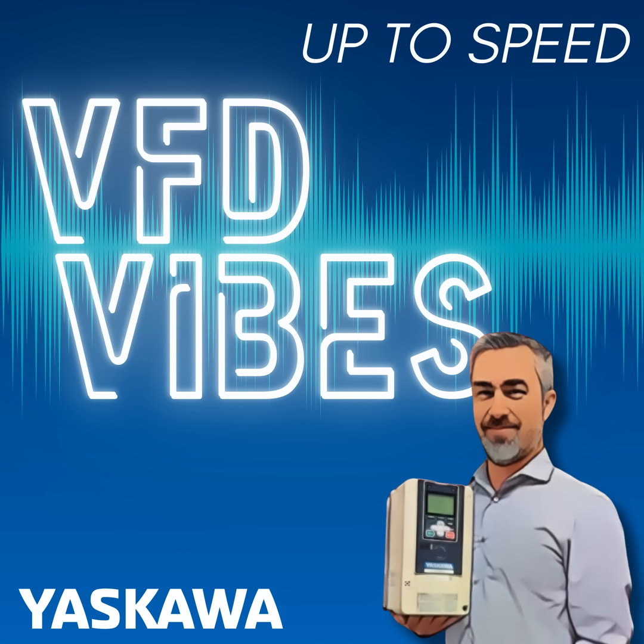Our listeners may be familiar with multi-pulse drive packages. These would be 12 or 18 pulse designs, and I use the word package because these aren't standalone drives. A multi-pulse drive package uses a phase-shifting transformer and additional rectifier blocks on the front end of the drive in the converter section to phase shift your incoming voltage so that you reduce your DC bus ripple and you reduce the amount of filtering your bus capacitors need to do, and that improves the harmonic performance by smoothing out that nonlinear current draw on the front end.